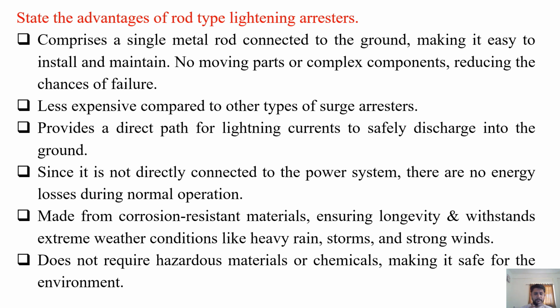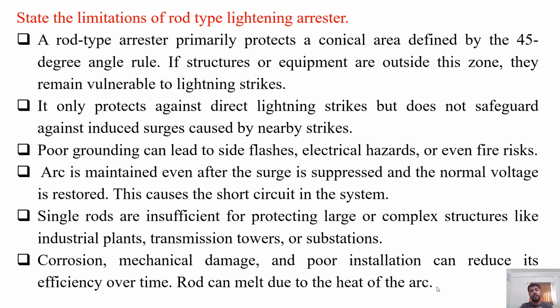It is made from corrosion resistant material, ensuring longevity and withstanding extreme weather conditions like heavy rain, storms, and strong winds. It does not require hazardous materials or chemicals, making it safe for the environment. So these are several advantages of rod type lightning arresters. State the limitations of rod type lightning arrester. So the rod type lightning arrester is one of the simplest methods of protection and the oldest method of protection.